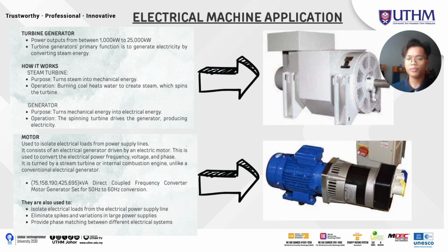And the motor generator is used to isolate electrical loads from power supply lines, and it consists of an electrical generator driven by an electric motor. This is used to convert the electrical power frequency, voltage, and phase. It is turned by the steam turbine or internal combustion engine, unlike a conventional electrical generator. Its rating starts from 75, 158, 190, 425, and 695 kVA direct coupled frequency converter motor generator set for 50 Hz to 60 Hz conversion. They are also used to isolate electrical loads from the electrical power supply line to eliminate spike and variation in large power supplies or provide phase matching between different electrical systems.